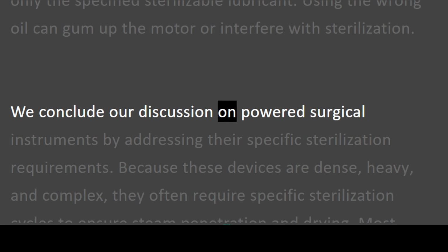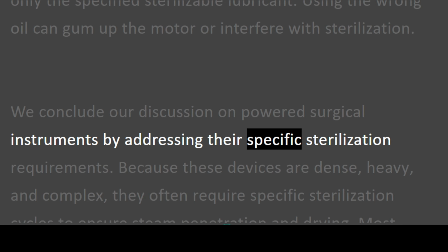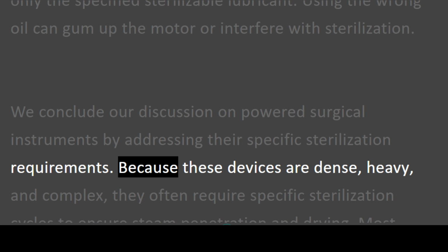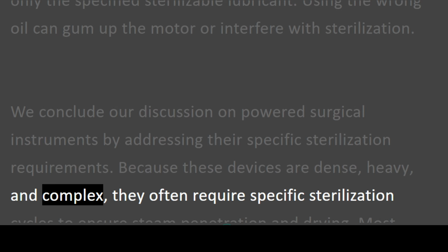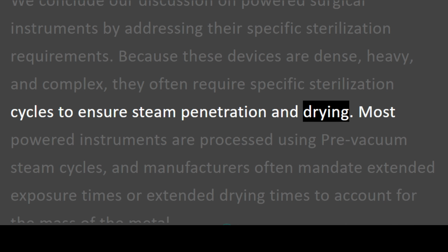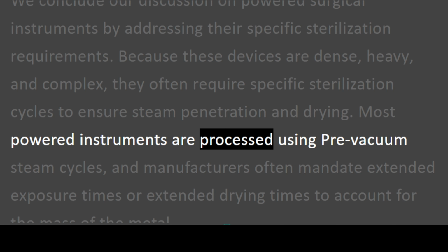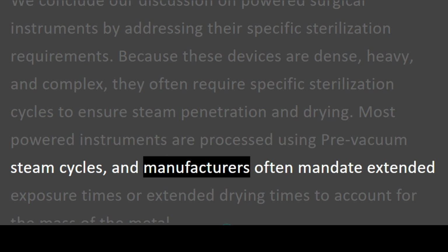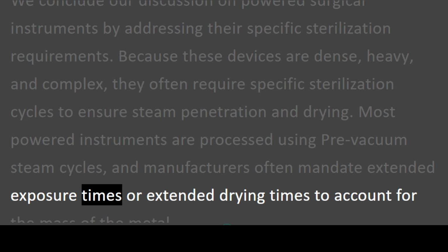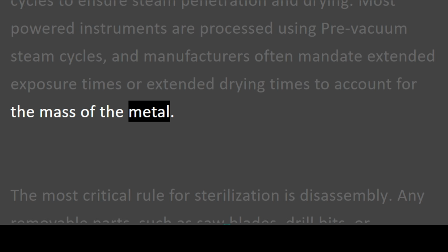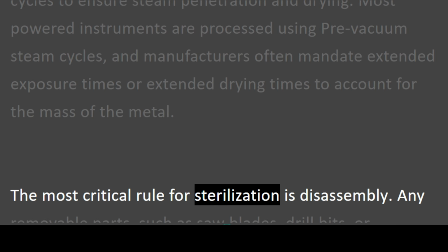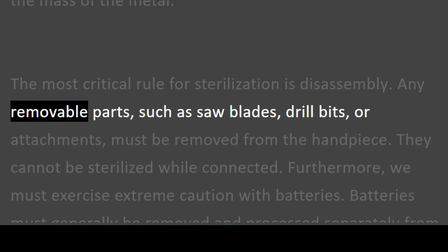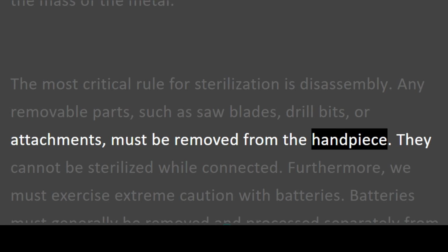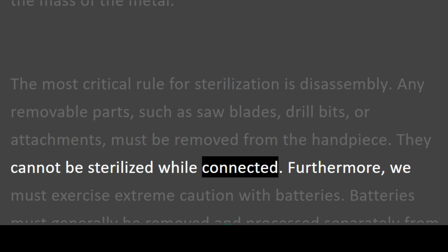We conclude our discussion on powered surgical instruments by addressing their specific sterilization requirements. Because these devices are dense, heavy, and complex, they often require specific sterilization cycles to ensure steam penetration and drying. Most powered instruments are processed using pre-vacuum steam cycles, and manufacturers often mandate extended exposure times or extended drying times to account for the mass of the metal. The most critical rule for sterilization is disassembly. Any removable parts, such as saw blades, drill bits, or attachments, must be removed from the handpiece. They cannot be sterilized while connected.